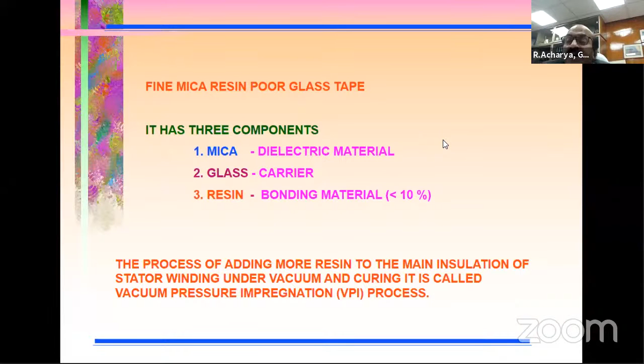So as far as the resin rich and resin poor systems are concerned, in the resin rich, the tapes contain almost 30 to 35% binder in a B stage. Whereas in the resin poor system, it has 8 to 10% of the binder with the accelerator. And during the VPI process, it absorbs the required amount of resin that has been supplemented, and it gives the required bonding strength. So this is the basic difference between resin rich and resin poor. Resin poor doesn't mean that it is poor in the final form. In the final form, every insulation contains 35 to 40% of the resin as a binder.